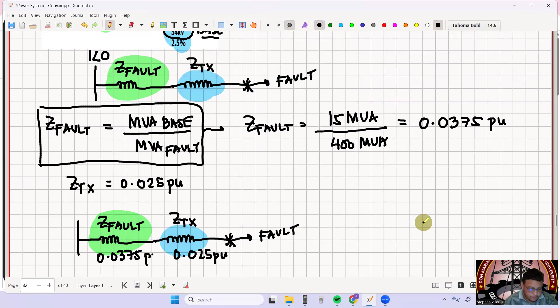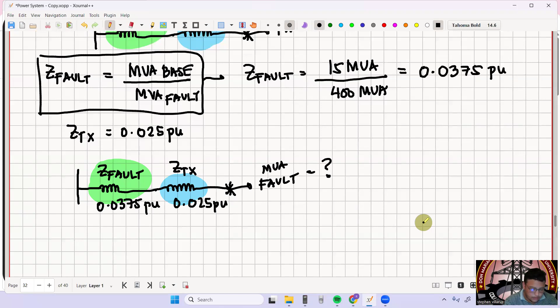So therefore paano na natin kukunin yung MVA fault? Dito lang yan manggagaling sa formula ulit natin, sa Z-fault na formula. Therefore, using the formula Z-fault is equal to MVA base all over MVA fault. So therefore yung MVA fault natin is equal to MVA base all over Z fault. Yung Z fault natin dito, since nakaseries lang naman yung impedances natin dito, therefore this is now equal to MVA base all over yung ating Z fault plus ZTX.